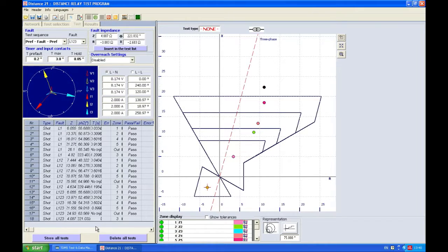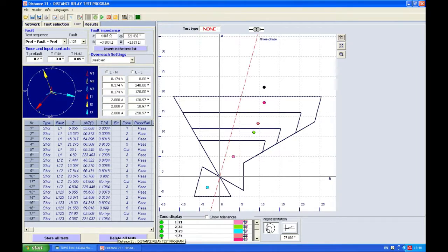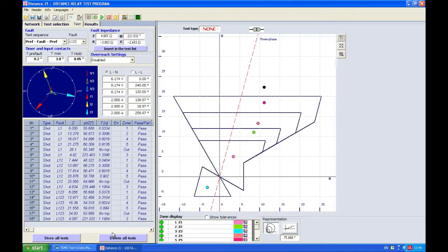Now having done that, I see I have a pass on all my tests. I will now do something to show you how you can repeat the test. So let's say that I'm going to repeat this test, but before that I'm going to remove the tripping signal from the DRTS, so we will intentionally have a bad result.